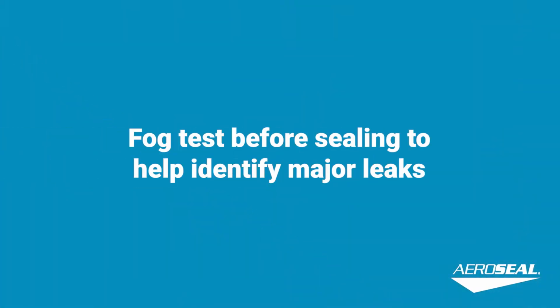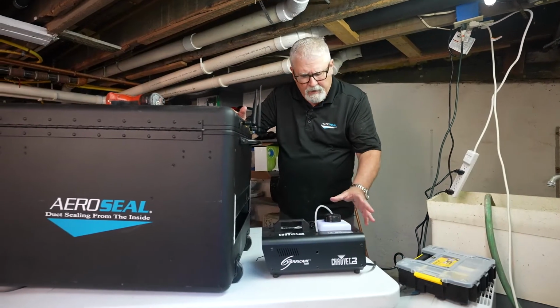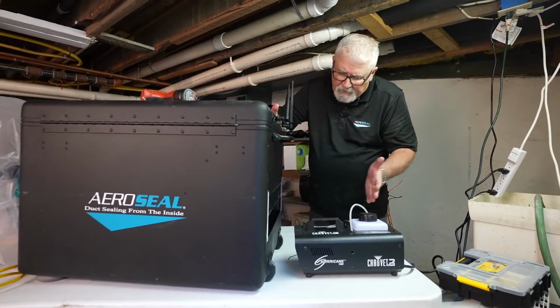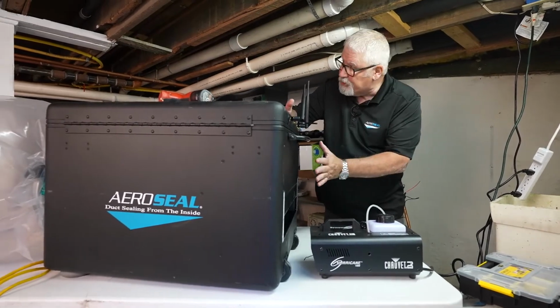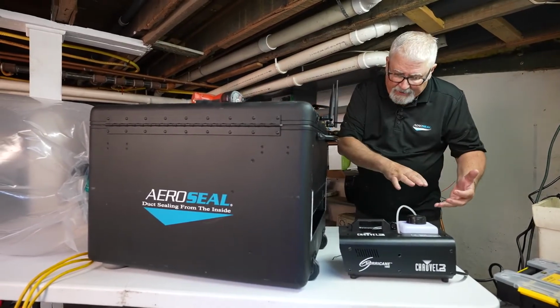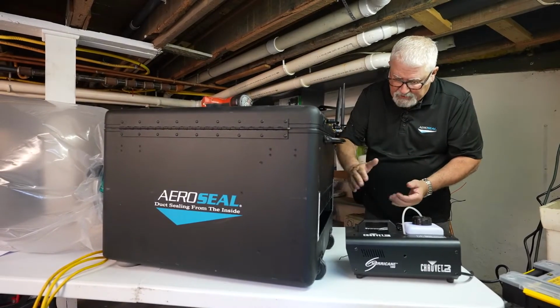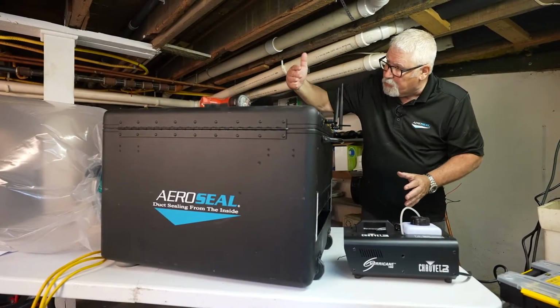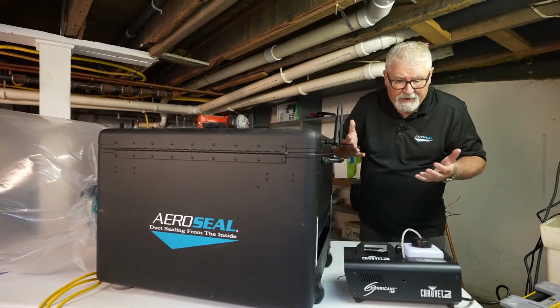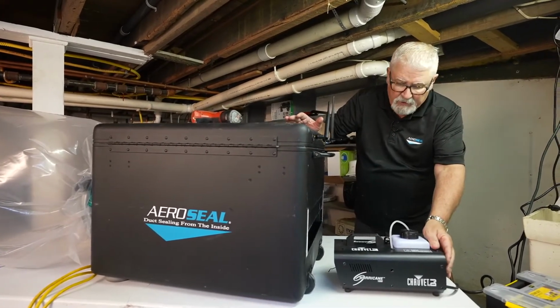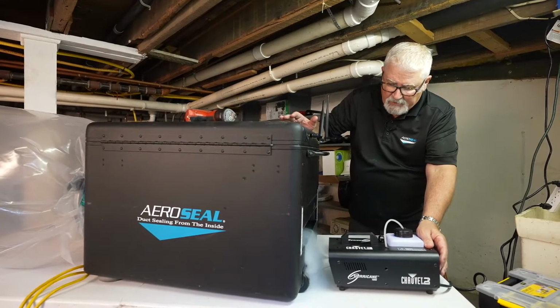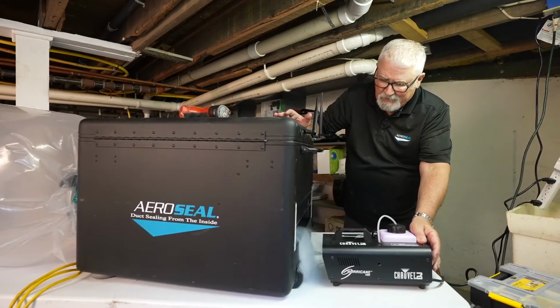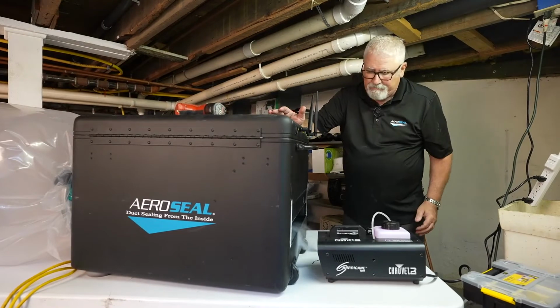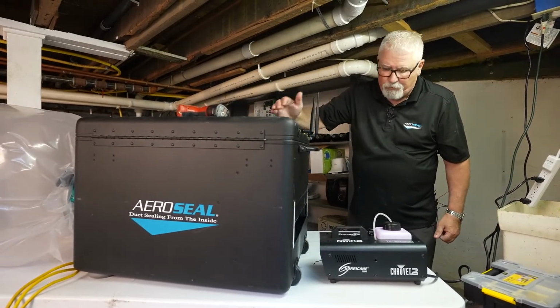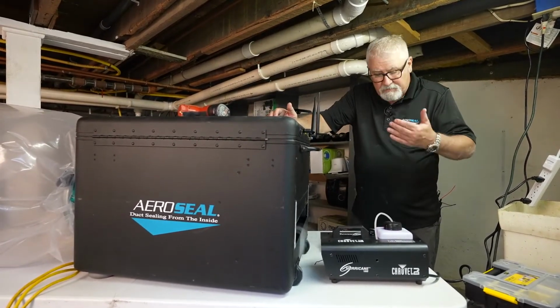Okay, let me explain what I've got going on here. This is just a fog machine, like a party fogger. We're going to turn this on. I've got my fan running, pushing air down through the duct system, and the fog is going to get pulled up and pushed inside. That way I can distinguish where it comes out, and you can find all the leaks in it. All I've got to do on this one is push this little button, and you can see that fog come pouring out and getting inside. Within a couple of seconds, the fog comes rolling out, and now we can distinguish that we have leakage.